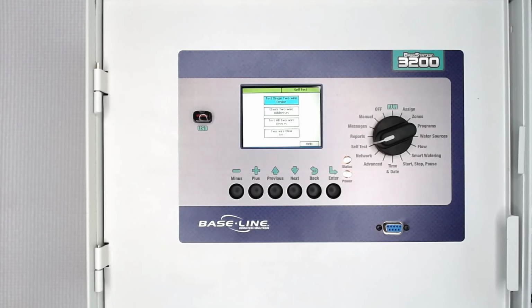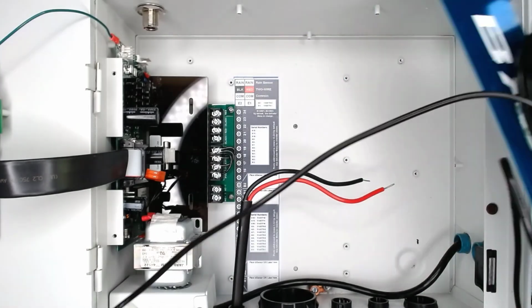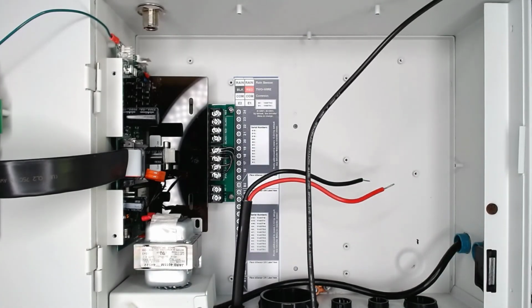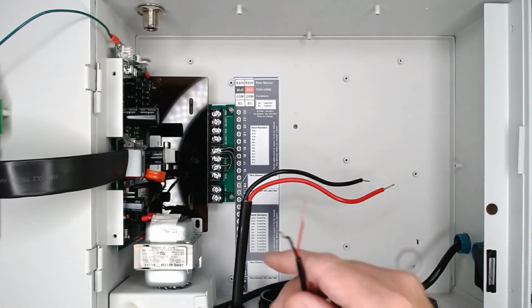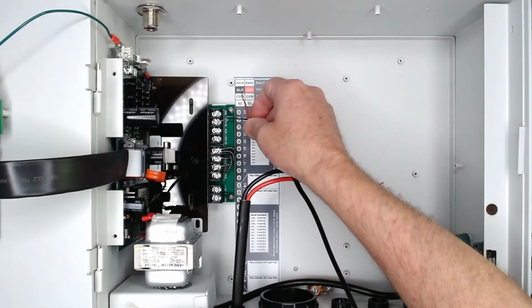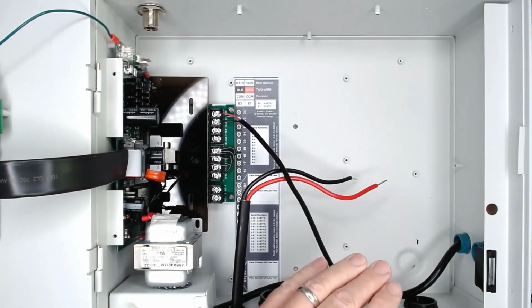While looking at the test results, keep in mind that the sensor measures volumetric moisture content. That means the sensor fully underwater reads about 35%. If the controller can find moisture on the sensor while it's directly connected, we eliminate the device as the issue. This means the problem is either due to installation, the wire path, or the splices on the wire path.